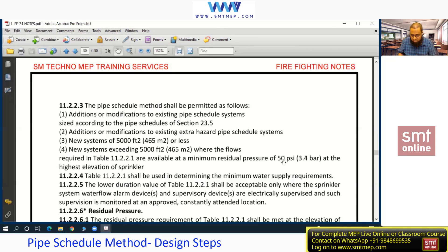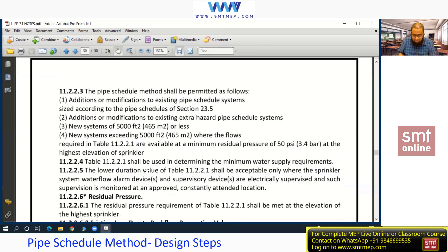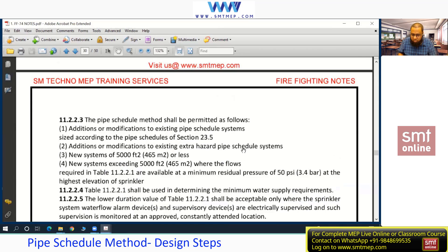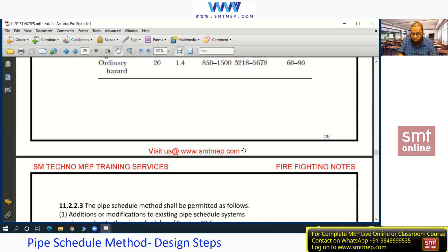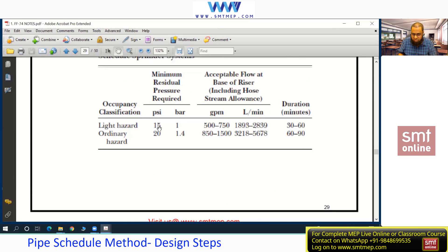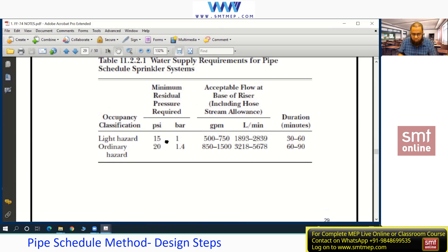So the pipe schedule method is applicable up to 5,000 square feet; above 5,000 square feet for a new project, the hydraulic method is applicable by default — we have two options. Regarding residual pressure: I'm not talking about total pressure. Residual pressure is the pressure we are going to maintain at the last sprinkler online. For light hazard, 15 psi; for ordinary hazard, 20 psi — useful to remember even for interviews.